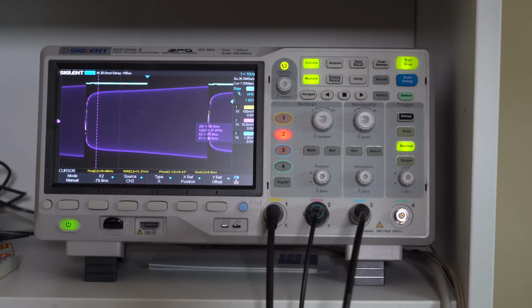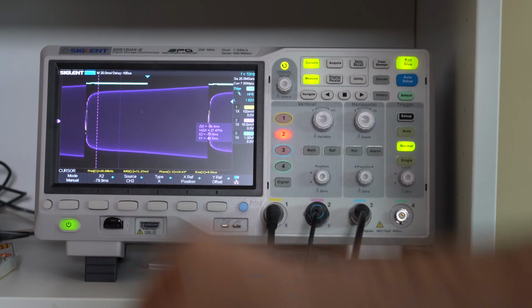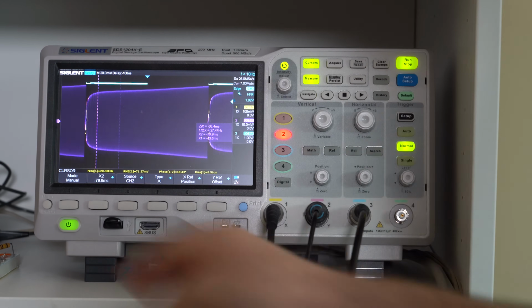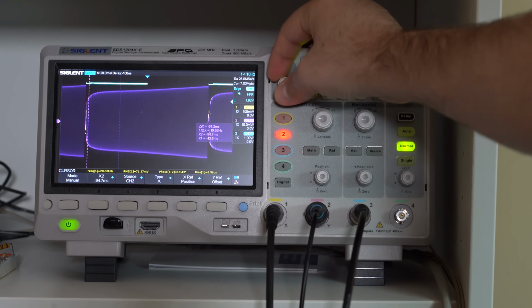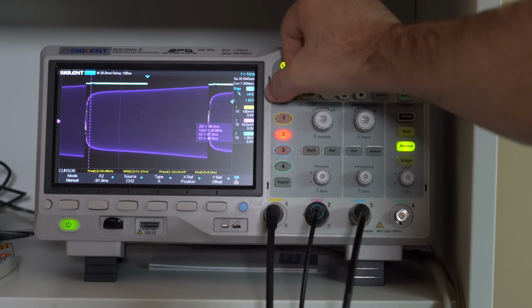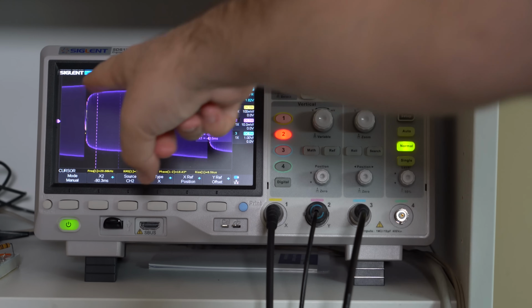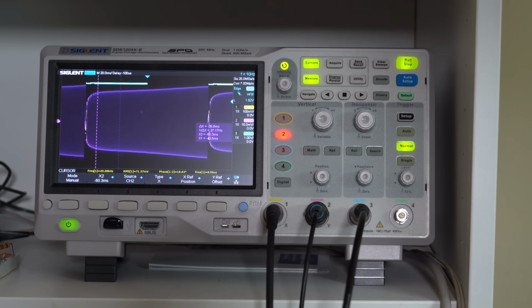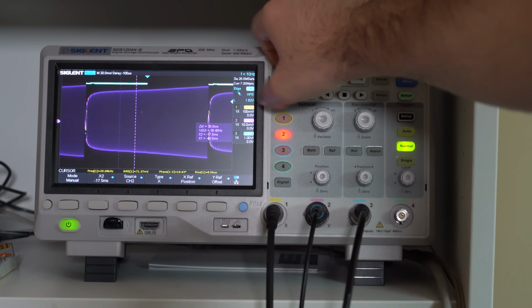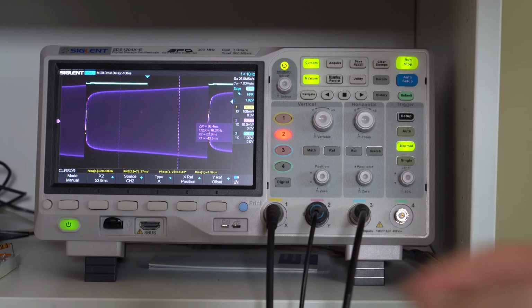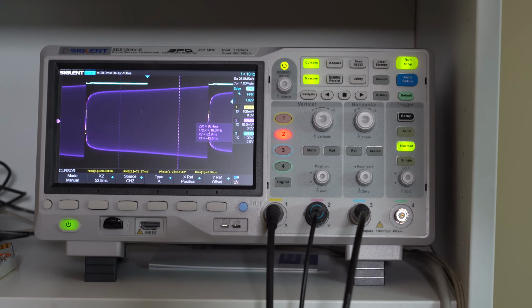Here's the response, and it pretty much confirms my suspicions. So as you can see, it's nowhere near flat, unfortunately, and since we know what the settings are, we know exactly how many hertz per division we have here. So we have 4000 hertz per division, which means that at the start of the sweep we have around 100 hertz, and here we have around 4100, which means that below 4 kilohertz you can see that the frequency response just drops. So we don't have that much low end, unfortunately, and the response is nowhere near flat, and it extends beyond the audio bandwidth, which is also not a good thing. So we should have a low pass characteristic here, and it should attenuate higher frequency, because otherwise it could be sensitive to radio frequency interference, I guess.